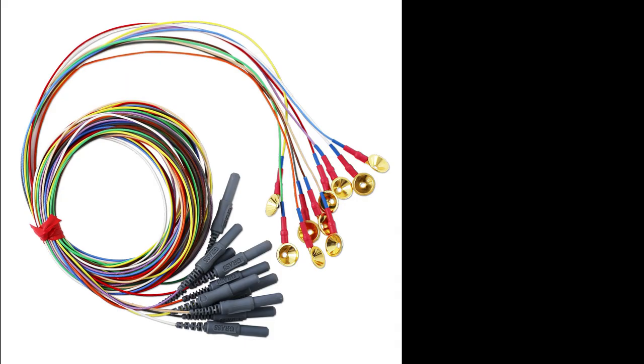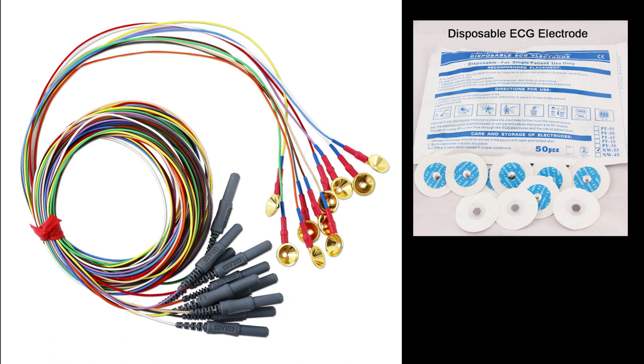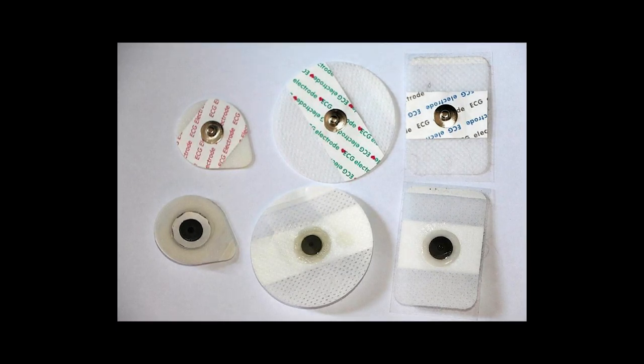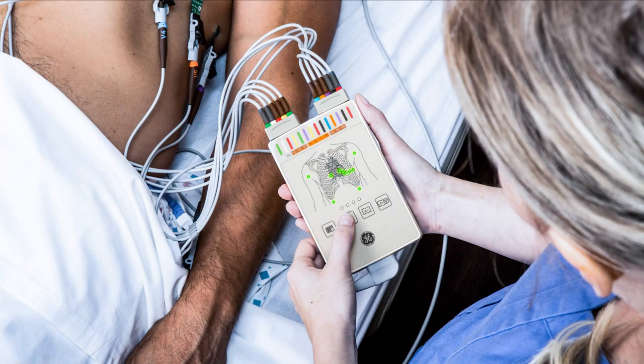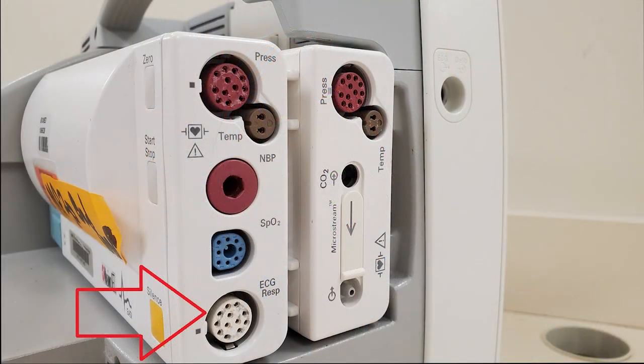There are reusable electrodes and disposable electrodes, with disposable being the most common. A disposable electrode has an outer adhesive surrounding a conductive gel center. The lead wire connects using a gator clip or a snap, and that lead wire connects to an acquisition module which collects all the analog waves and converts them to a digital signal for the ECG to interpret. Acquisition modules also act as an isolator between the patient and the ECG computer, protecting the patient from possible leakage currents and preserving the electrical integrity of the patient's ECG signal.